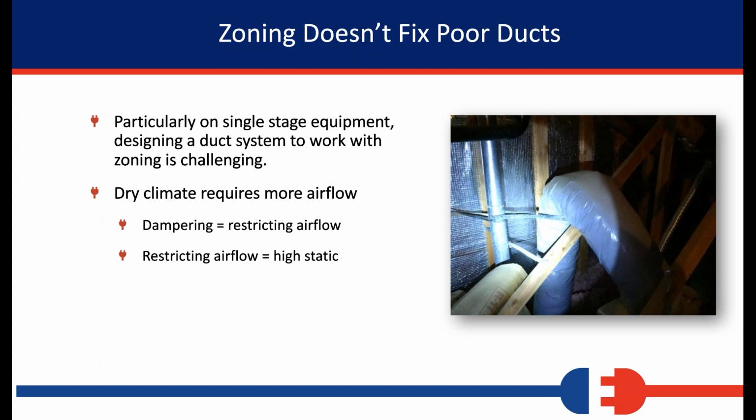And the other thing we know here in California, we're blessed with this thing called dry climate. If anybody in the audience has ever spent any time on the East Coast, Texas, or one of those places where we have really high humidity in the summertime, that takes a completely different strategy of HVAC install to handle that additional humidity that's in the air, like all this latent heat removal that we have to do with our systems. We don't have to deal with that in California, so we're really blessed, right? So we need systems out here in California that have lots of sensible cooling, which means the energy we're using from the system is actually being used to cool the air in the house, and we're not wasting a bunch of energy trying to draw humidity out of the house.